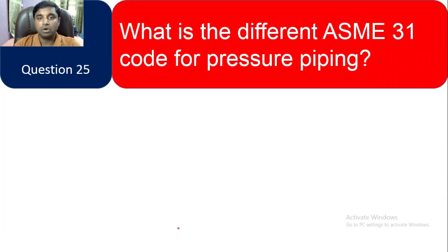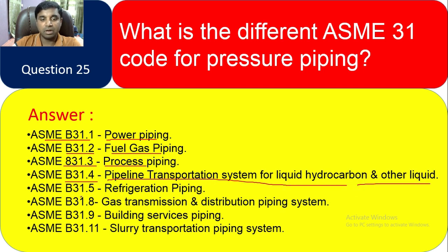Question 25: What are the different ASME B31 codes for pressure piping? ASME B31.1 — Power Piping; B31.2 — Fuel Gas Piping; B31.3 — Process Piping; B31.4 — Pipeline Transportation Systems for Liquid Hydrocarbons and Other Liquids; B31.5 — Refrigeration Piping; B31.8 — Gas Transportation and Distribution Piping Systems; B31.9 — Building Services Piping; B31.11 — Slurry Transportation Piping Systems.